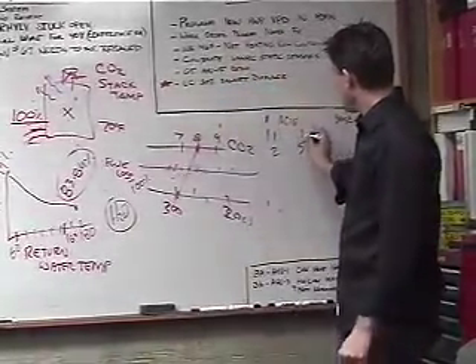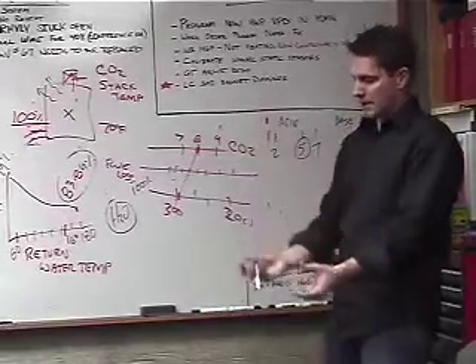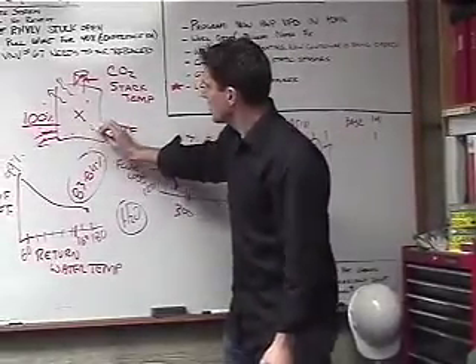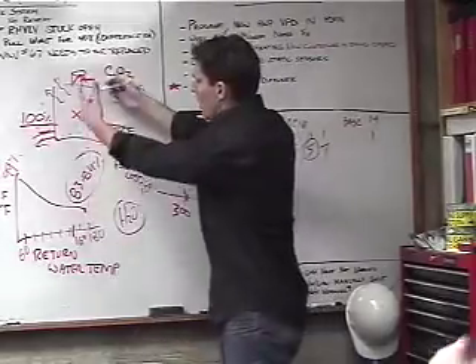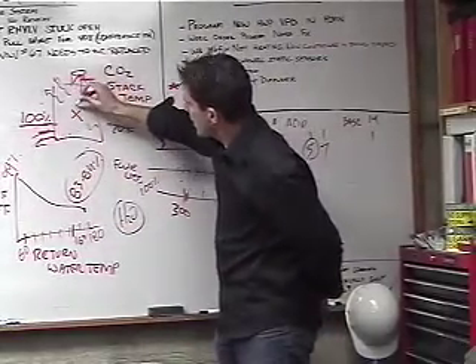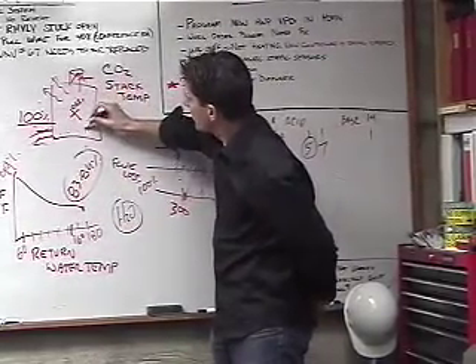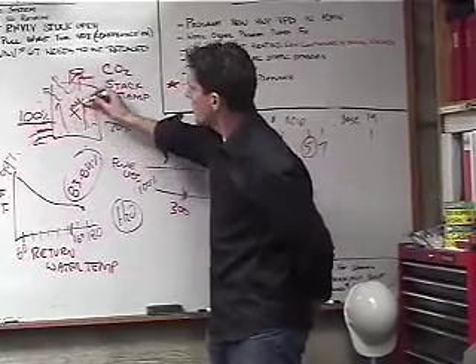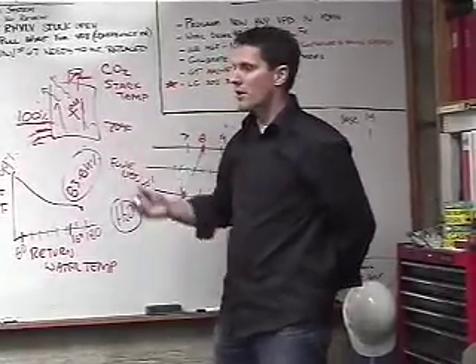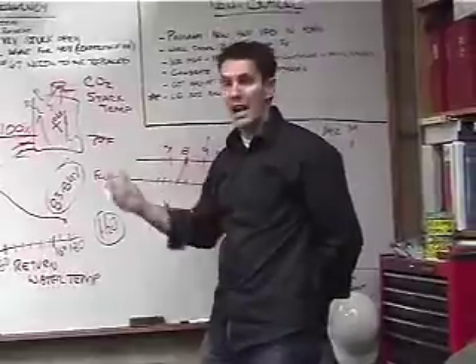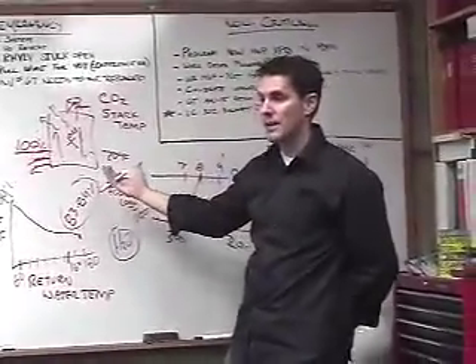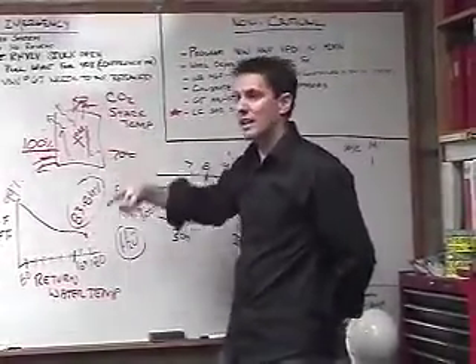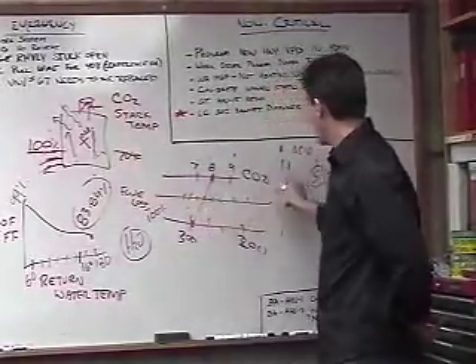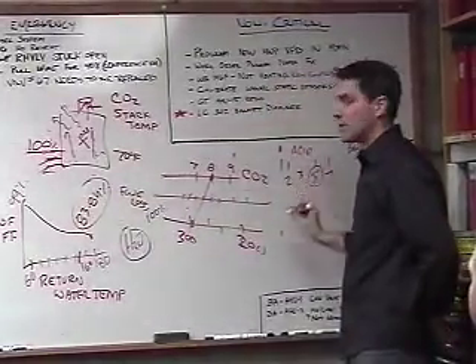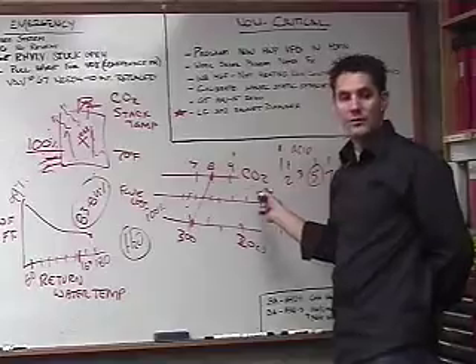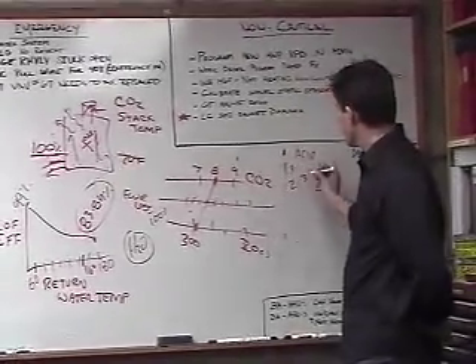You can get cycles of concentration because with typical old school boilers, you're creating water vapor. It cools off because you've got a cold heat exchanger inside. My flue gases travel up, and we start to condense towards the top. Where do the water droplets go? Back down to the hot zone. So what happens to them? They re-evaporate. So we get a cycle of concentration that occurs, and that drives my acid level down to 3. That'll eat through the metal even faster. So we try to prevent that.